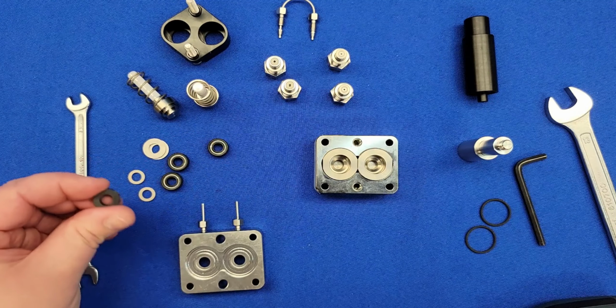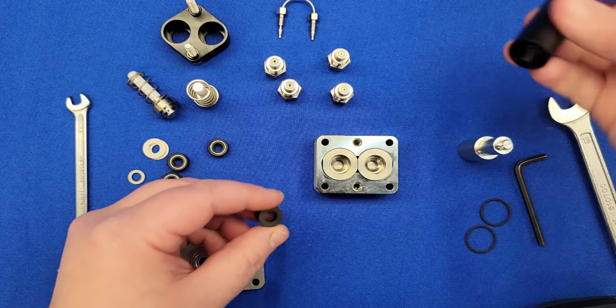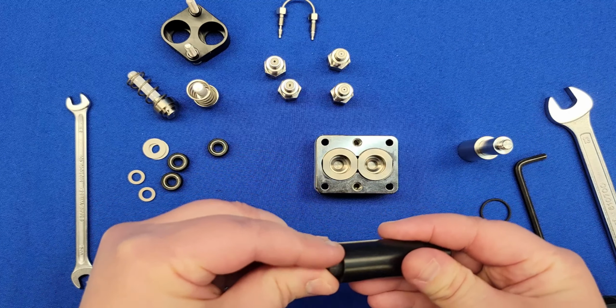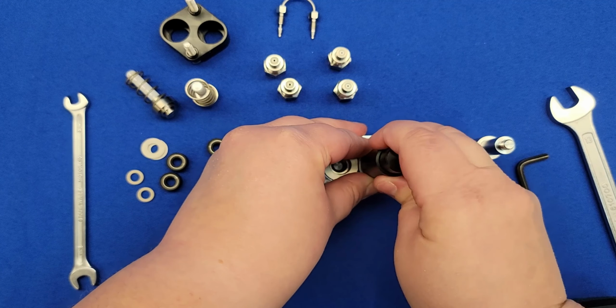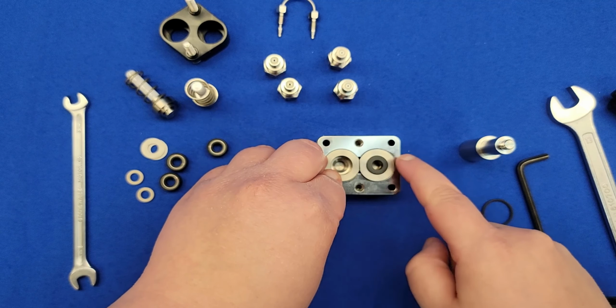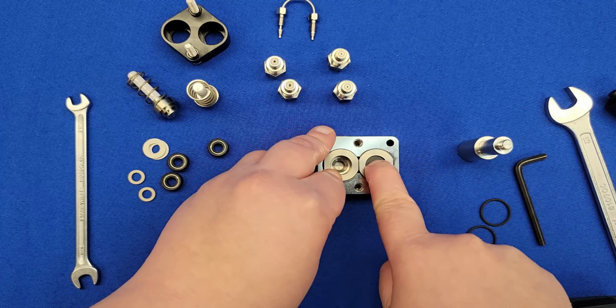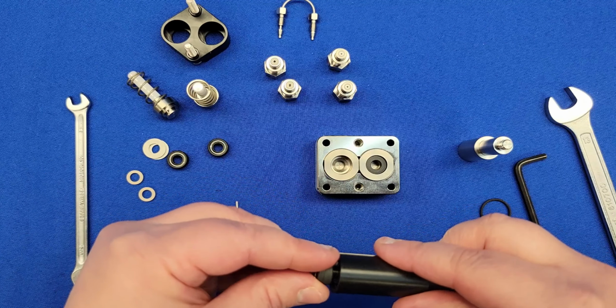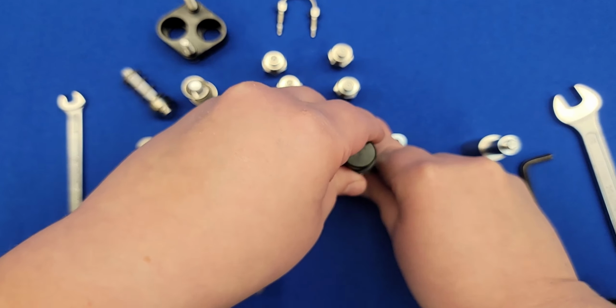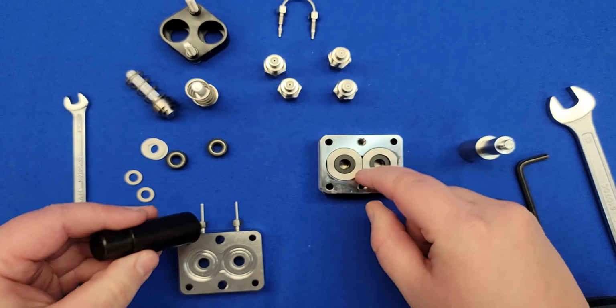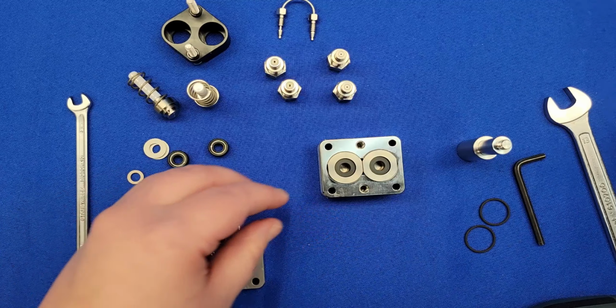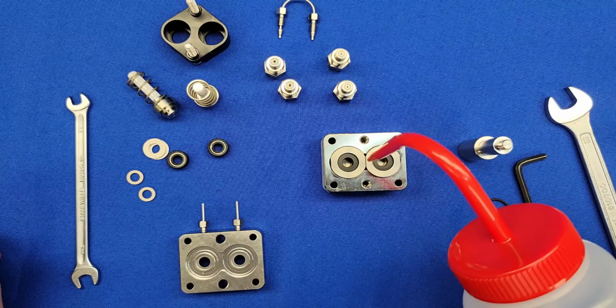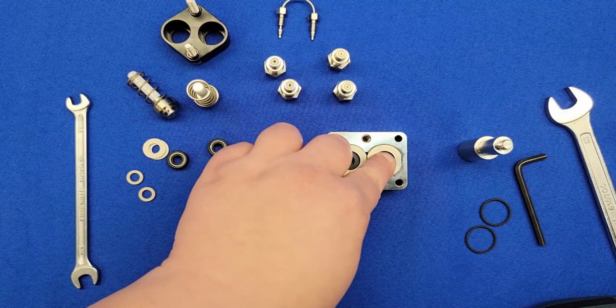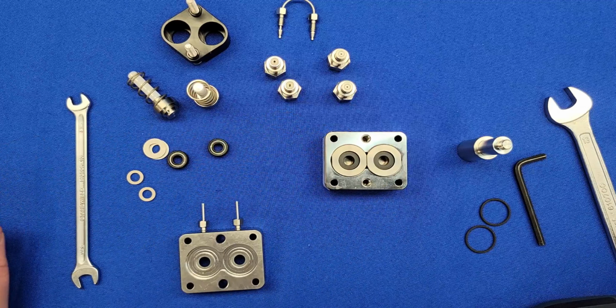So we have to put the seals back. What you do is use your insertion tool, put it in, and press it back. In our case, it's going to bring the insert up, and you see there's a little bit of elevation, so you just press it down. The insertion tool just helps to make sure that everything is straight and you're not crooking the seal when you're inserting it. And then press down. At this stage, it's also good to use a little bit of solvent to make sure the seals are going to expand in the position that they're supposed to be in.